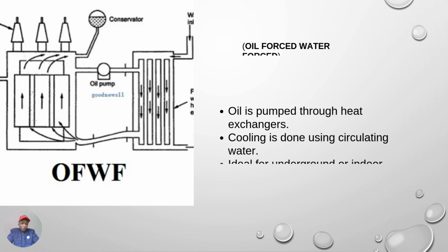Next, we have OFWF - oil forced, water forced. This is an improvement on OFAF because instead of air, you use water, since water is a better coolant than air. Oil is pumped through heat exchangers, and cooling is done using circulating water instead of air. This method is ideal for underground or indoor settings, and while it is the most complex, it is also the most efficient method.